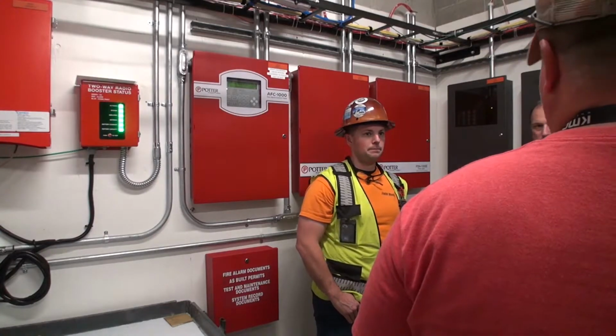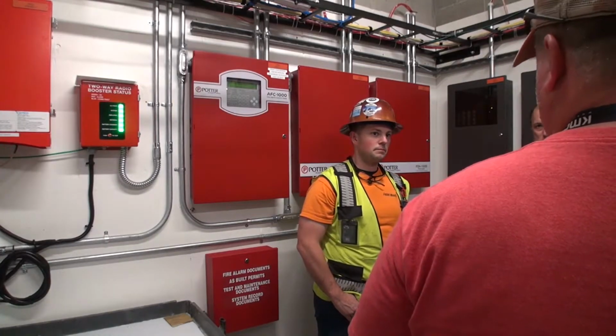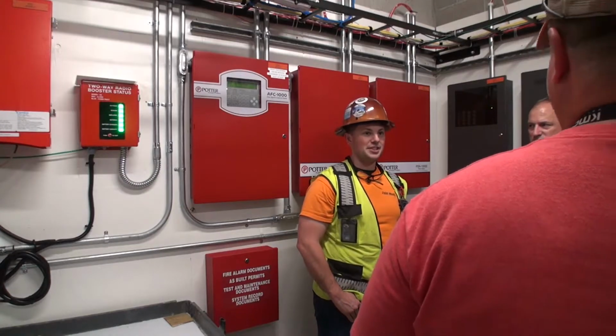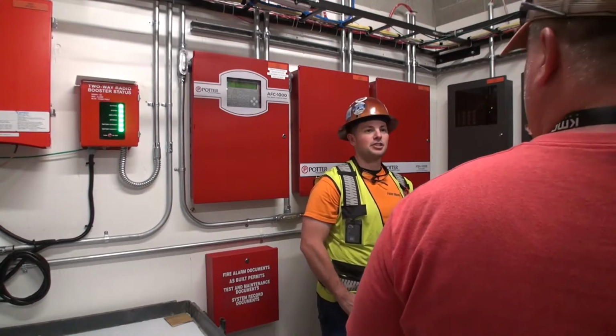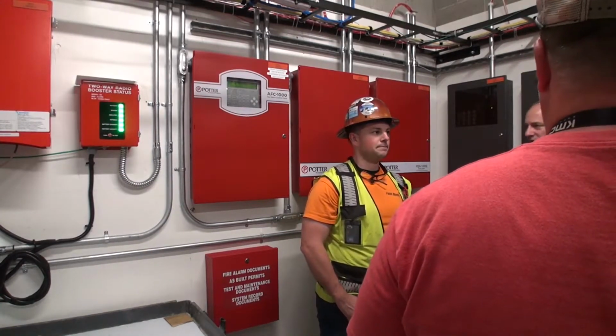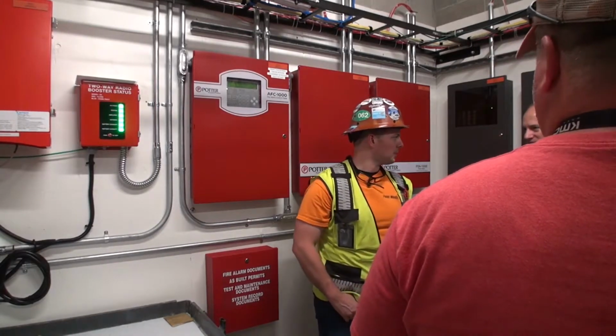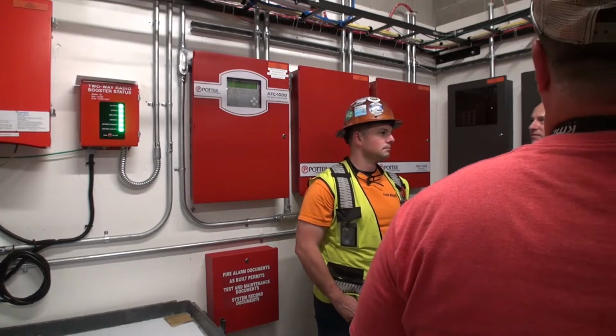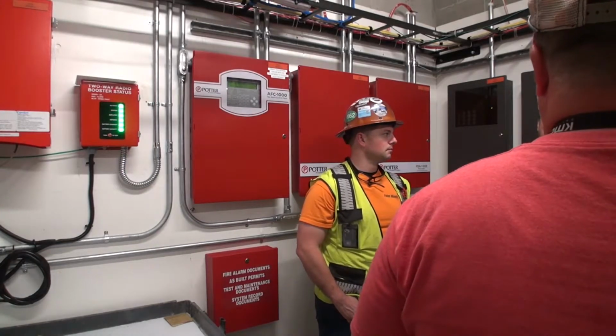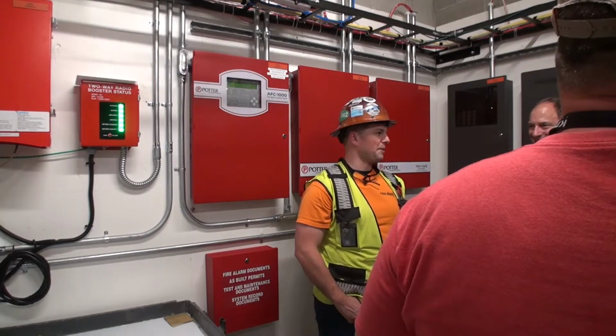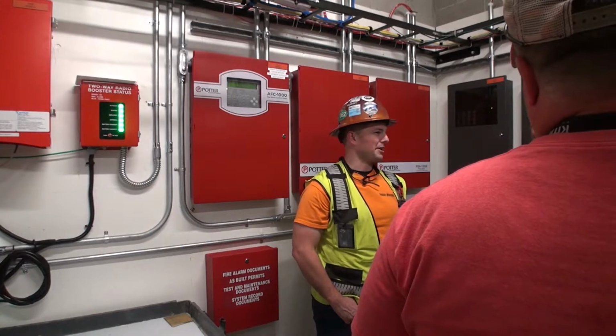So you didn't need an SLC expander or anything like that? Oh, there's lots of SLC. Yeah, I believe there are 5 SLC loops here. Wow, okay. Are they all derived from here, or are they spread out? No, there's no more than 2 loops on a panel. Oh, okay. We had one where we had lots. I believe it's in your spec that there are no more than 2 loops allowed on a panel.